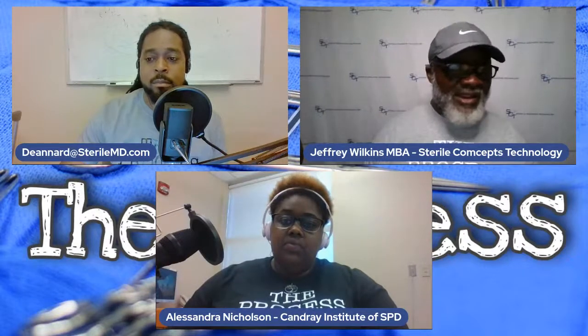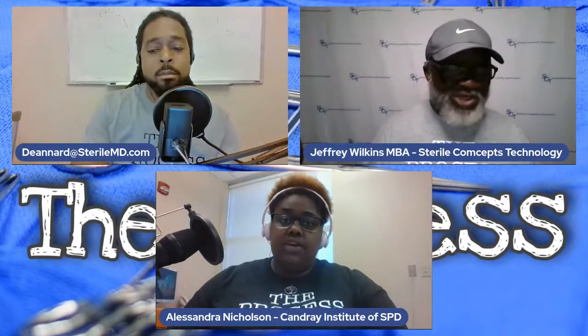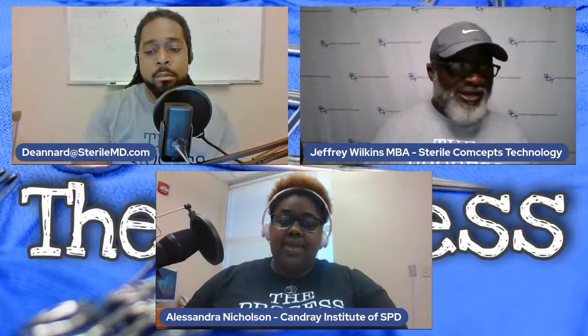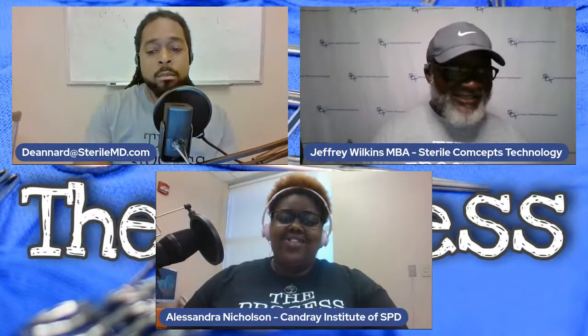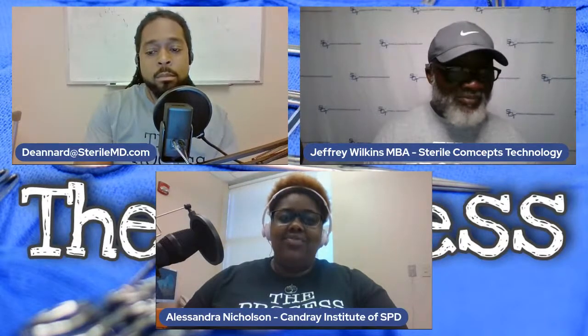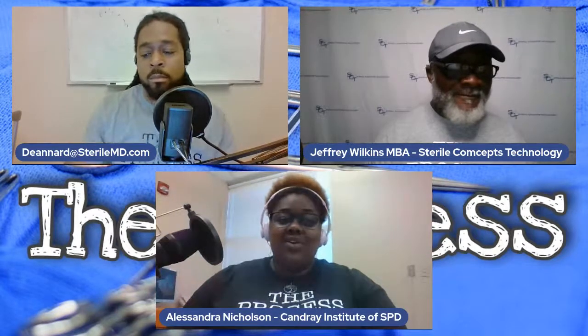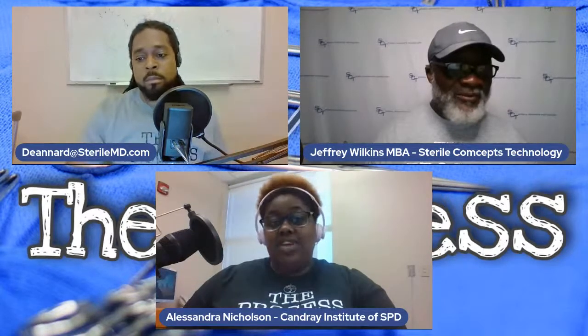Because without it, and it's amazing, remember we didn't have IFUs before. We were just processing every single thing the same, using the same detergent, the same water. And I really feel like that's trying to make a comeback with these general IFUs that I'm seeing more and more. Guys, watch out for those. Definitely keep copies of those and read them if you haven't.